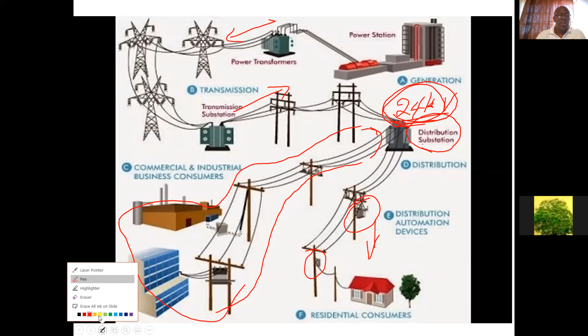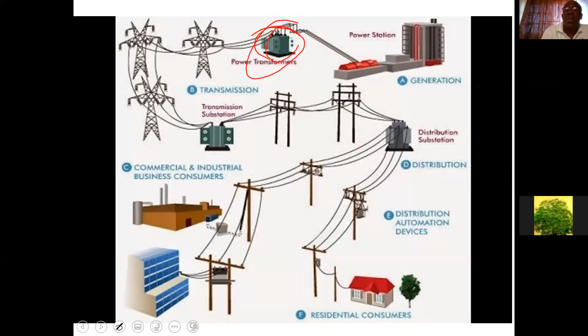However, in most instances, what we assume for your generators - remember I said that your generators would be at 13.8 in terms of terminal voltage. By the way, the limiting factor for your generator would be its ability for cooling, so that is why your generators will be up to 13.8, up to a maximum of 24K. So these being your generators, the general assumption is that it also has the transformers linked to them, as I showed you in the previous diagram.